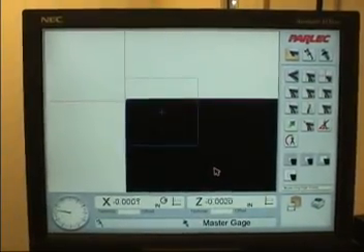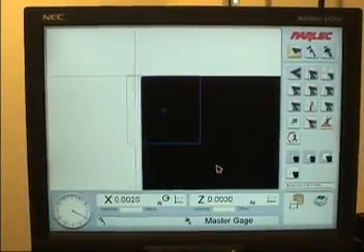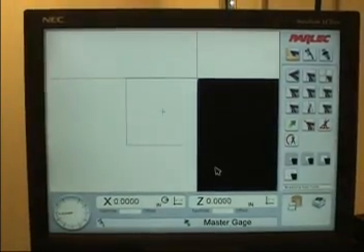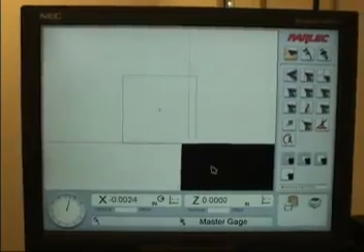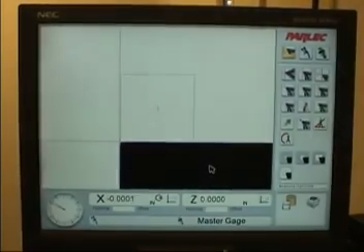Measure the gauge at the 4 corners of the measuring window. The measurements should not exceed 2/10. If the measurement exceeds 2/10, then run the pixel calibration procedure.